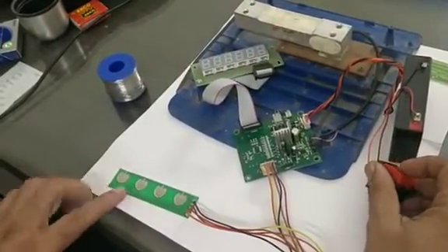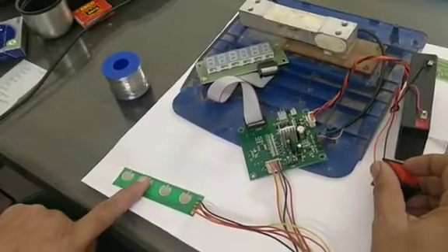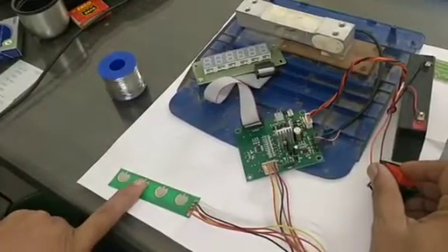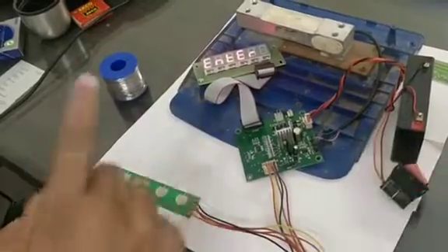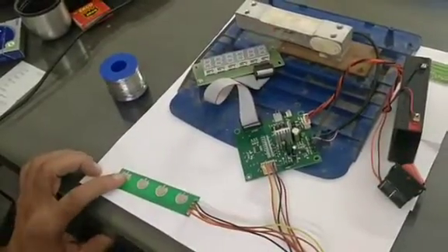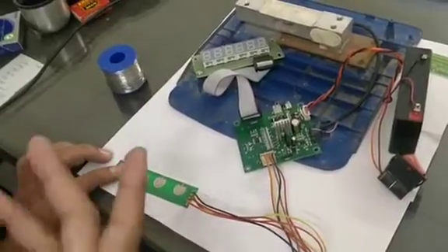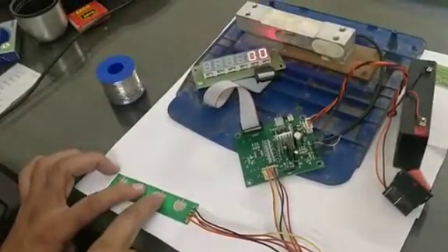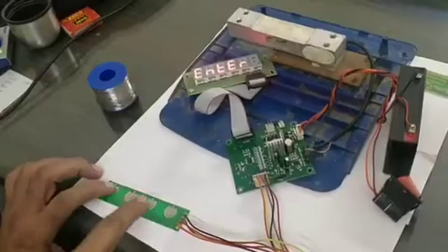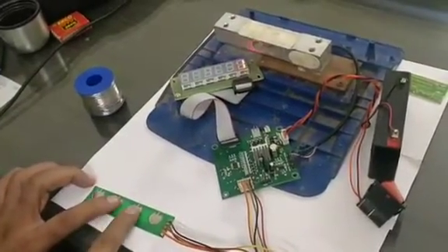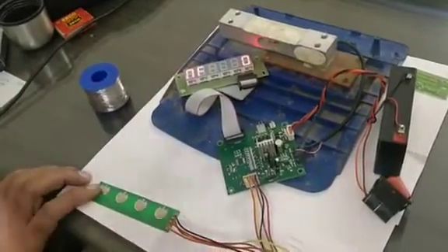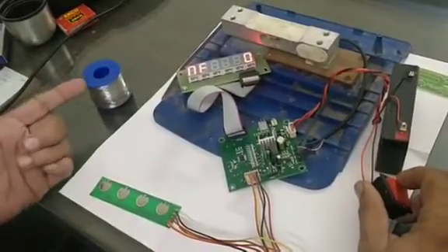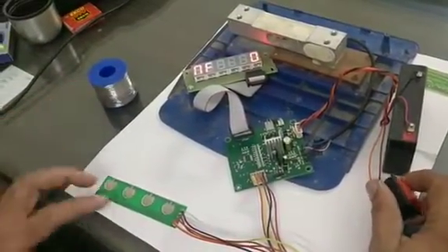I will show you the password which I put which is 10. Press key 2 and switch on display show enter. Here it is asking for the password which is 10. If I put wrong password then it will go again enter but if I put right password which is 10 then it will open the parameter. Same thing is in the calibration also.